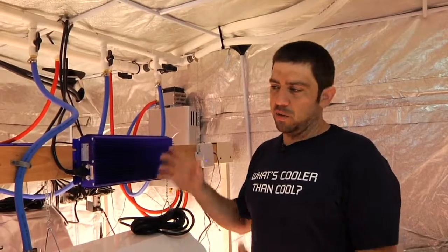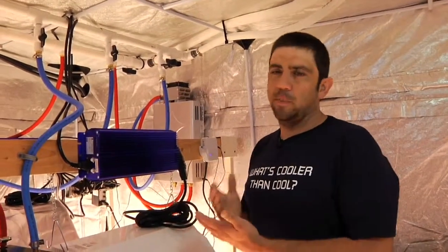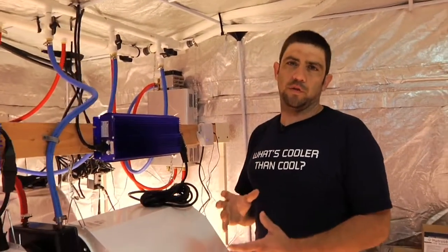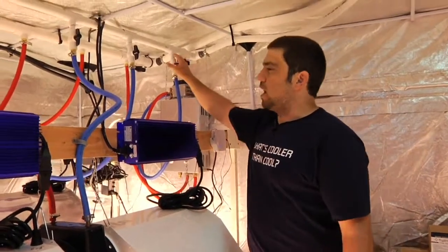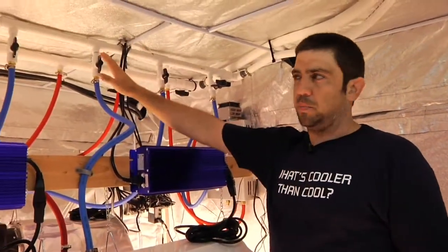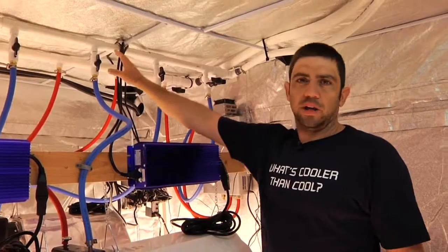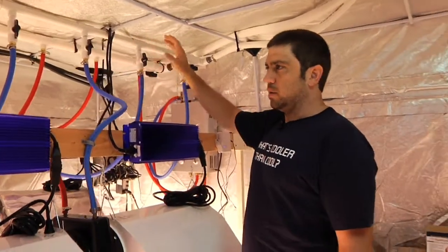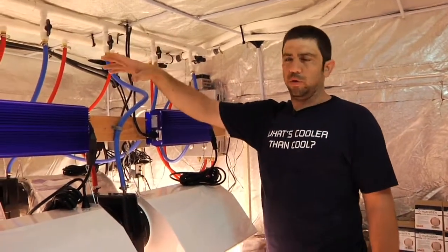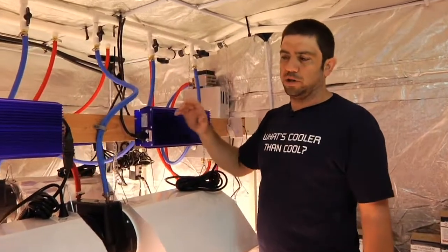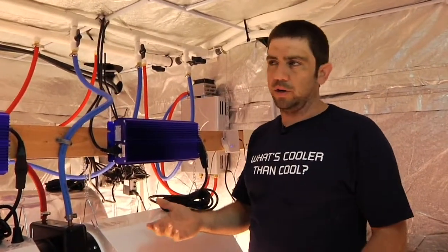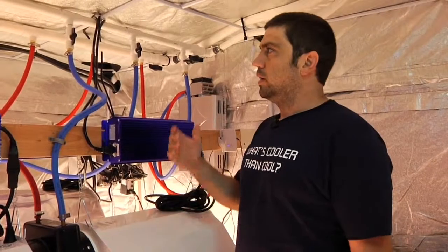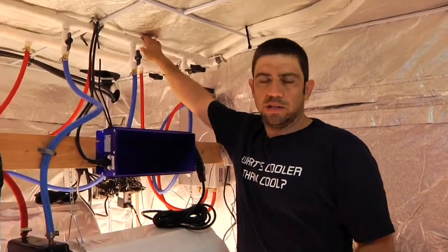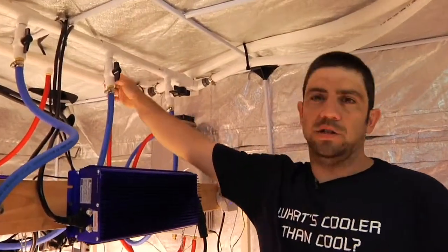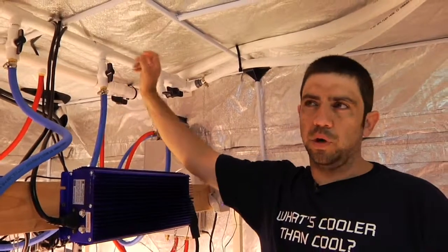You can daisy chain 1 or 2 ice boxes together, but a proper setup should use a distribution manifold system. You see, we've got valves on each one of these supply lines. This is going to regulate the flow through your equipment. Some equipment you can run full bore with the water flow. Some equipment you may want to turn back, like our nutrient reservoir cooler. You don't want it to be too cold. Now, what we've done is we've got a 1-inch line coming in, and we've got a 1.25 inch going back out. And that's really important.